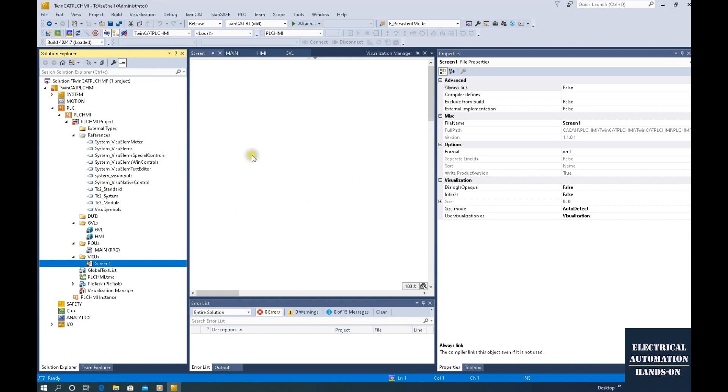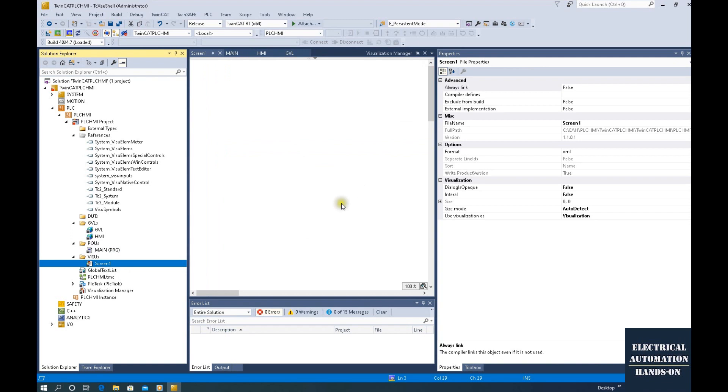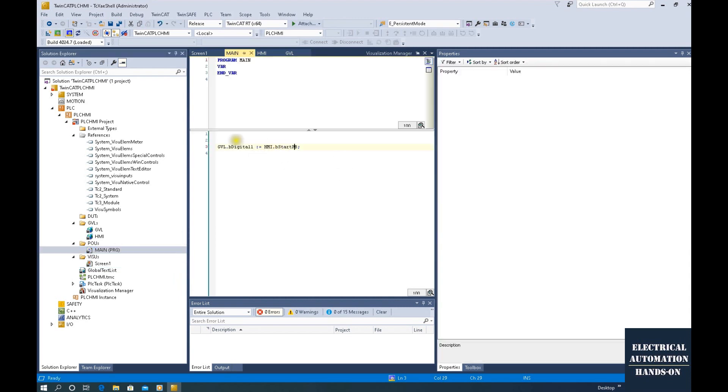And from this HMI world, basically this HMI, it has two styles. One style is we create an individual screen here. And the screen can jump back and forth between each other. The screen will be only used within this PLC test. That means the screen, once we activate this project, this screen can show up. However, if you are using the actual Beckhoff controller and once the controller reboot, so this screen will not be activated. This is the one style. And this style basically will be used as a test wheel. For example, after we program some tag or some logic, and you want to use this screen as a temporary test wheel and a temporary data monitor, so you can use this style. And the beauty thing of this style, since there is no .exe execution HMI file, so we do not need to use any license. Its main purpose is testing some tag or testing some data. This is used to facilitate the PLC commissioning.